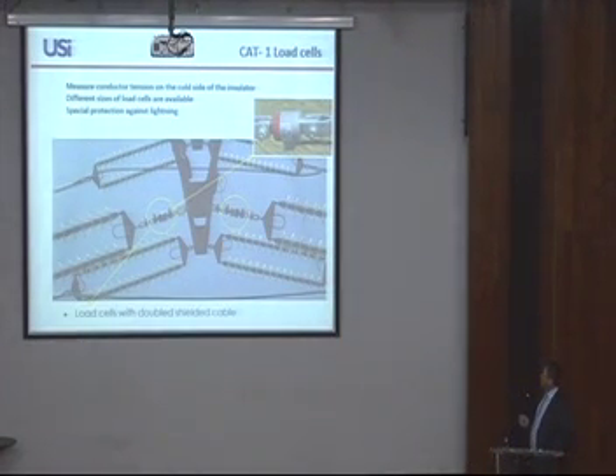Okay, now, how do our technologies look? With USI, we have two different technologies. One is what we call the CAT1. It has been used within CEMIG before. This CAT1 is based on tension measurement. So we are measuring the mechanical tension between the insulator strings and the dead end cross arm on two sides, so measuring in two directions, two line sections, where we have different sizes of load cells for different mechanical requirements, and we have had special protection against lightning for 10 years now, mainly to avoid damage through lightning strikes.